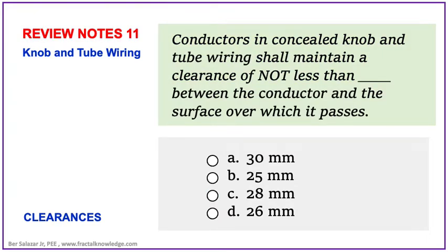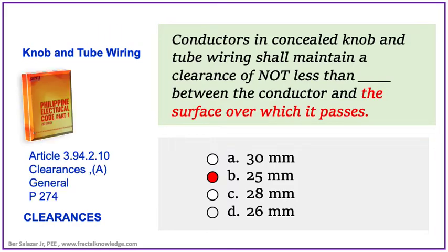Another possible problem asks: what is the clearance between conductors and the surface over which it passes? The answer can be found in 2017 PEC Article 3.94, page 274, specifically section 3.94.2.10 Clearances. The keyword here is 'between conductors and surface over which it passes.' The answer is 25 mm — that's letter B. Be careful because the numbers are close; if 25 mm is not in the choices, the possible answer is 26 mm. The exact value is 25 mm or 1 inch.